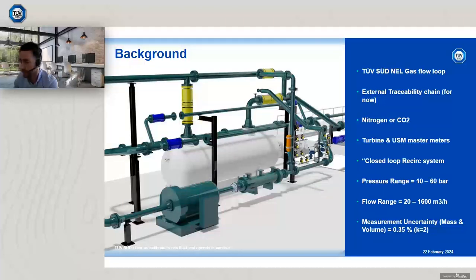We have a combination of turbine and ultrasonic master meters, predominantly using ultrasonic master meters, but we also have turbine master meters that we can also use. The uncertainty of this facility is 0.35% for mass and volume at K equals 2. In terms of pressure, we can operate from 10 to 60 bar for nitrogen. For CO2 it's slightly less due to the phase envelope of CO2, so we operate from 10 to nominally 40-45 bar, because if you pressurize CO2 you start to go into the liquid phase. And the flow range is nominally 20 to 1600 meter cubed per hour.